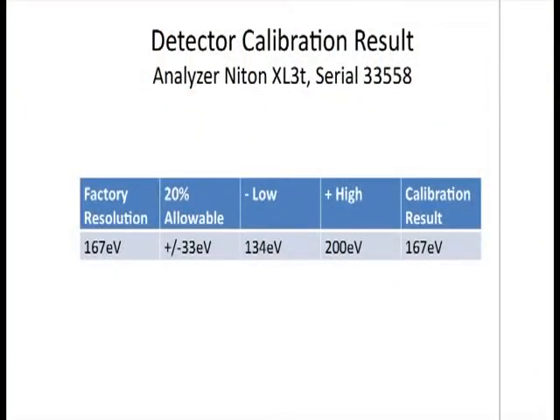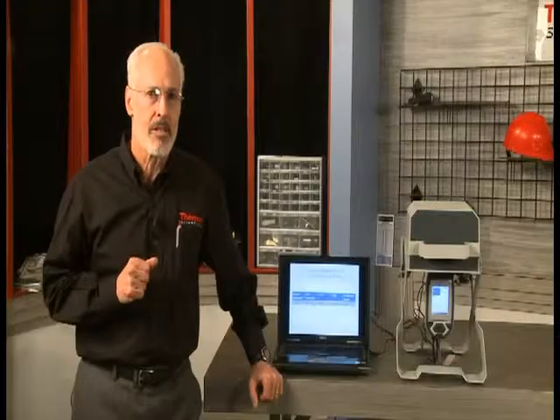Let's take a look at the resolution from the detector calibration that we just did. We see it as 167 eV, or electron volts, the standard unit of measurement for detector resolution. 20% of 167 is plus or minus 33 eV. This will give you a lower limit value of 134 eV and an upper limit value of 200 eV. Any computed resolution value outside this range may indicate a problem with the detector. In the unlikely event that this should happen, please contact your nearest Thermo Scientific Niton Analyzers Service Department.